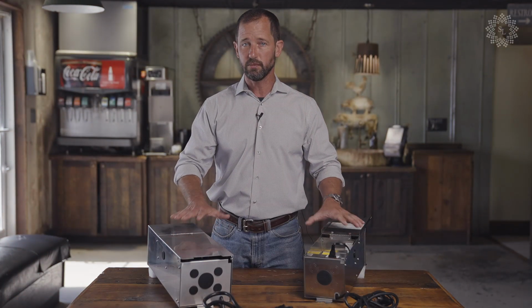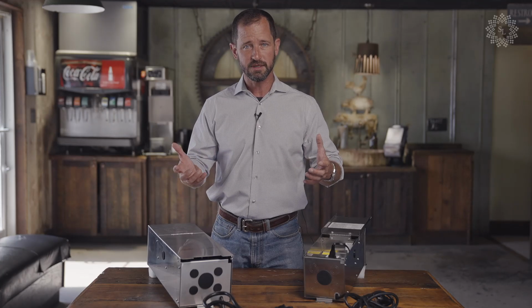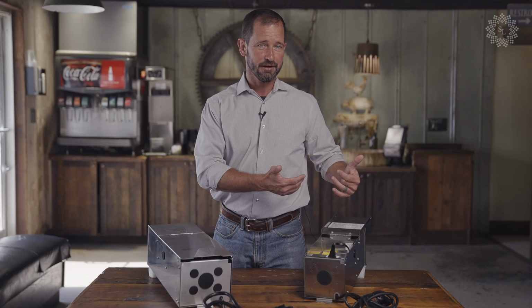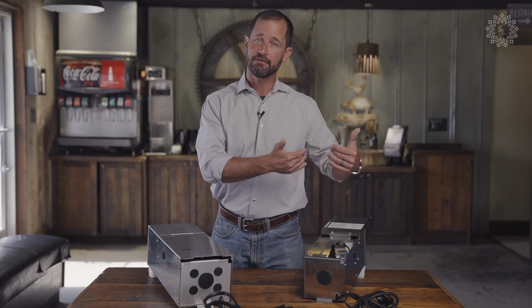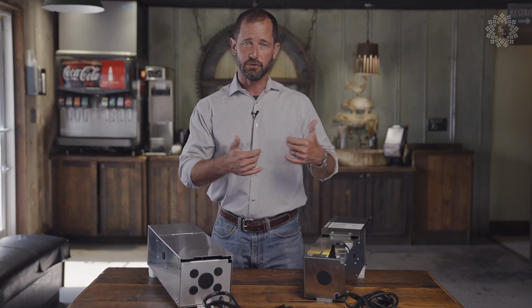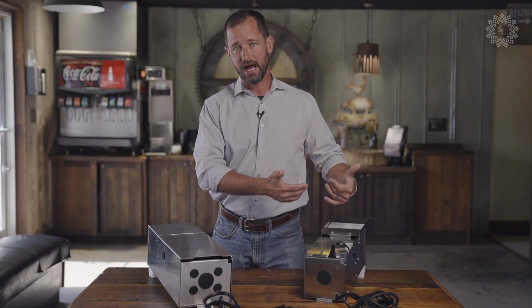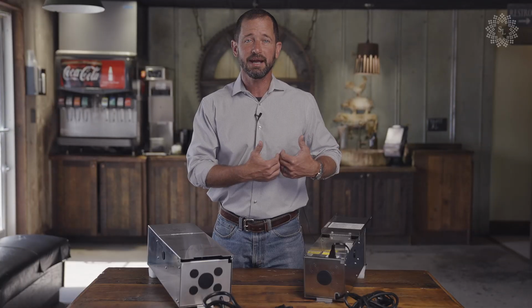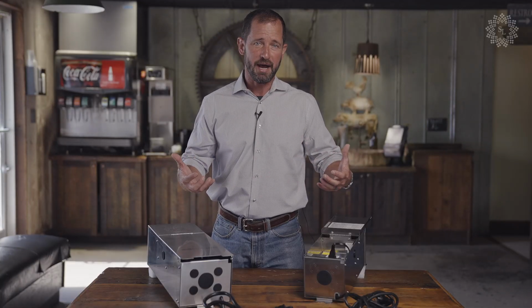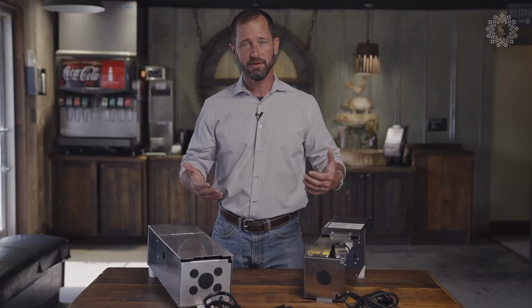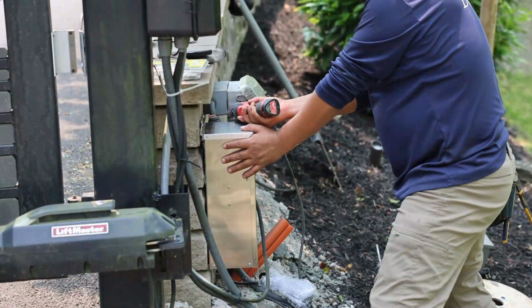300 and 600 are the most used transformers. Very simple reasons why. It's only a $10 difference on manufacturing to have a 150 watt versus a 300 watt transformer. I recommend in my company, I always want to have more power than I need, so if a customer wants to add in, I'm not having to swap out transformers.